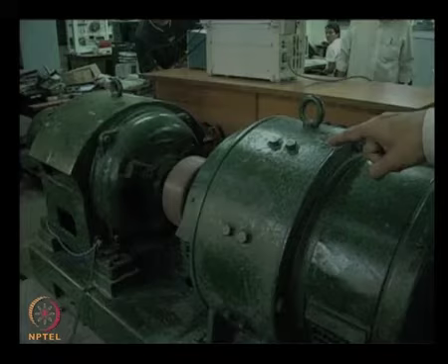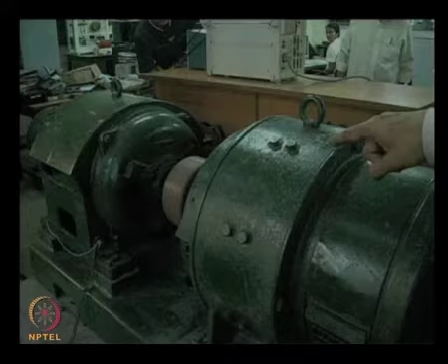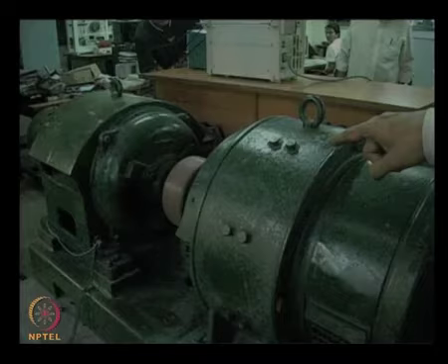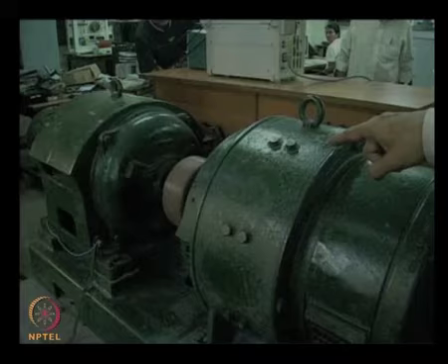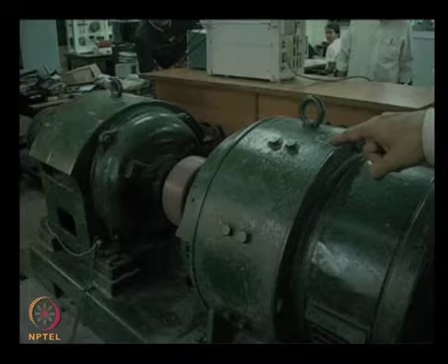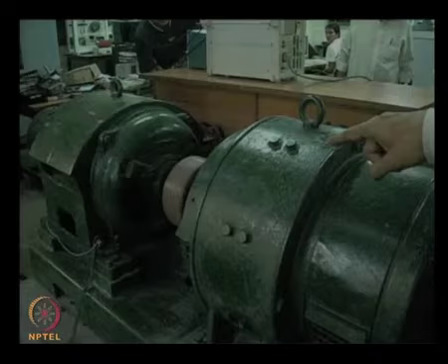I will start this demonstration now. The machine has already been started and it is running and has been excited to give a very low voltage, about 20 volts line to line RMS at the terminals of the machine. We will apply a dead short circuit under these conditions. Let us observe the current waveforms for the phase A, B and C under these circumstances.